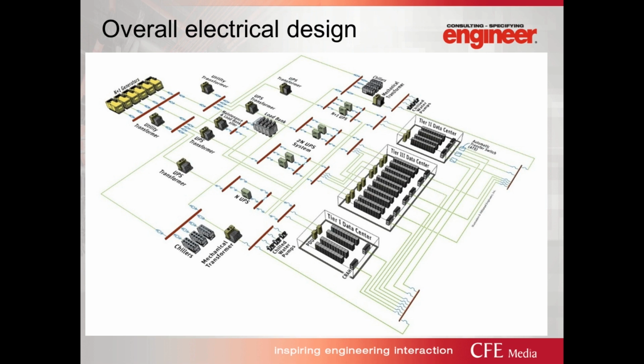So there's a lot of data going around, and if that's not clearly defined in your OPR about who's doing what, oftentimes you're going to double dimension that and have either two people pricing up the same scope of work, or worse, neither of them, and you have a scope gap there. So with all of these levels of remote monitoring going on in a data center, you need to be very clear about what points you want to look at and who's going to look at them and who's going to gather those points so that you can appropriately budget for it.